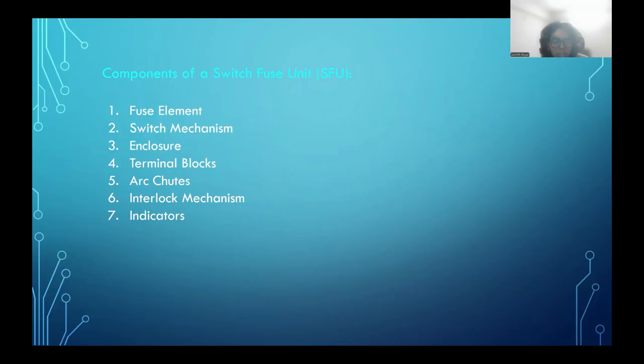Third, enclosure. It is housed in a robust enclosure, typically made of sheet steel and powder coated for rust protection. This ensures safety and prevents accidental contact with live parts and protects the internal components from environmental factors such as rusting. Fourth, terminal block. These are used for connecting incoming or outgoing wires. Fifth, arc chutes. These components help extinguish any electrical arcs that may occur when the circuit is open, ensuring safety during operation.